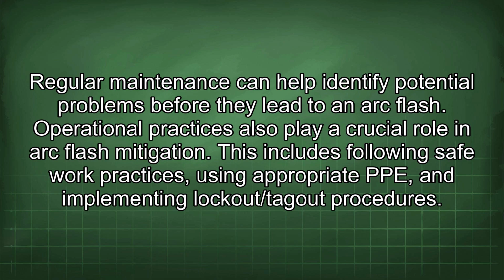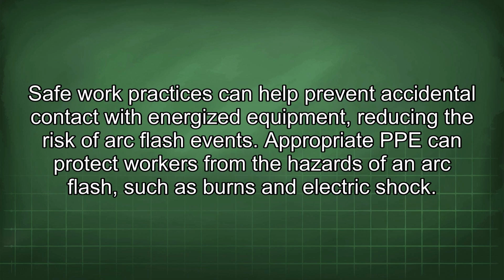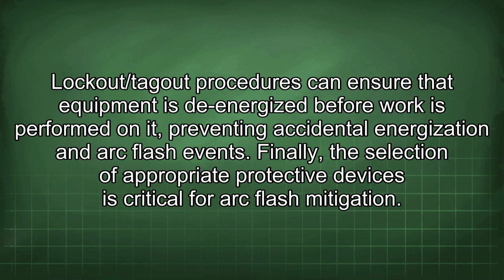Operational practices also play a crucial role in arc flash mitigation. This includes following safe work practices, using appropriate PPE, and implementing lockout/tagout procedures. Safe work practices can help prevent accidental contact with energized equipment, reducing the risk of arc flash events. Appropriate PPE can protect workers from the hazards of an arc flash, such as burns and electric shock. Lockout/tagout procedures can ensure that equipment is de-energized before work is performed on it, preventing accidental energization and arc flash events. Finally, the selection of appropriate protective devices is critical for arc flash mitigation.